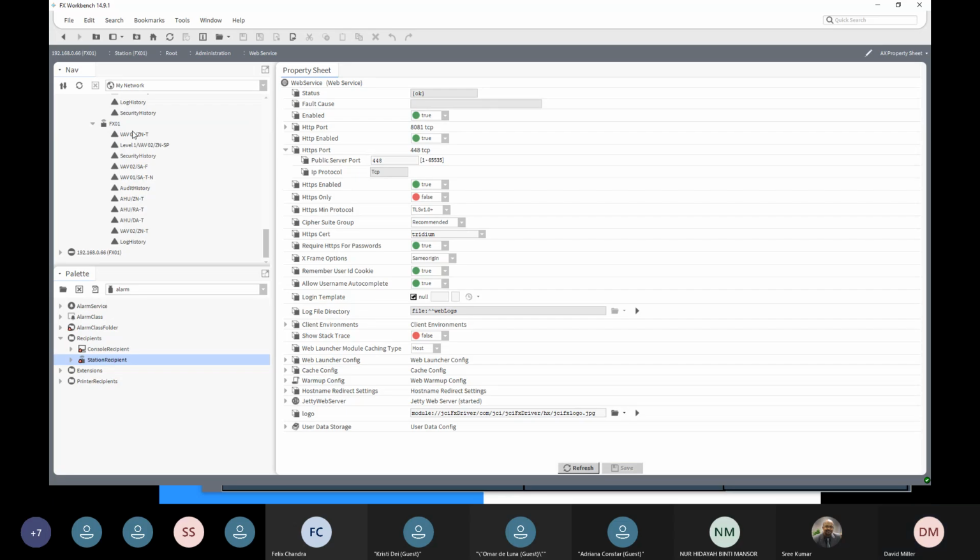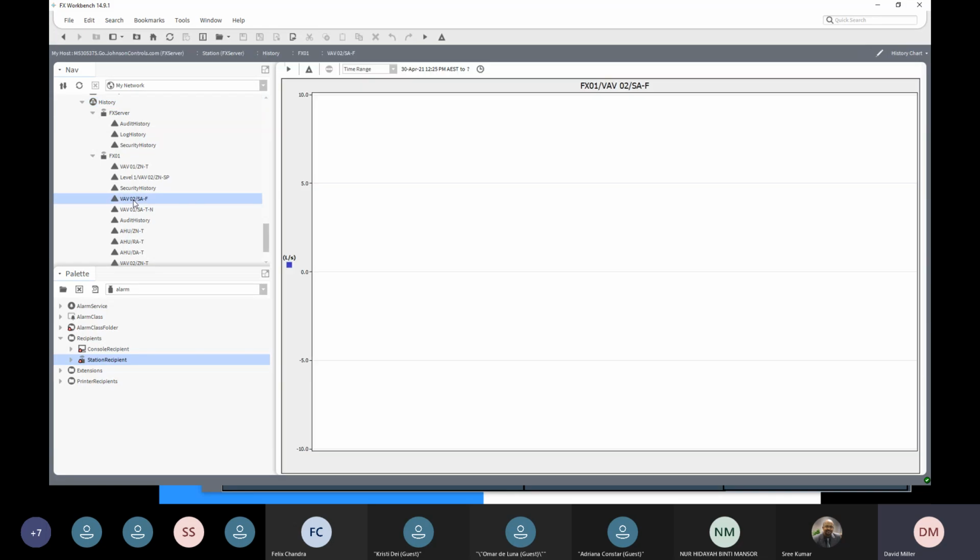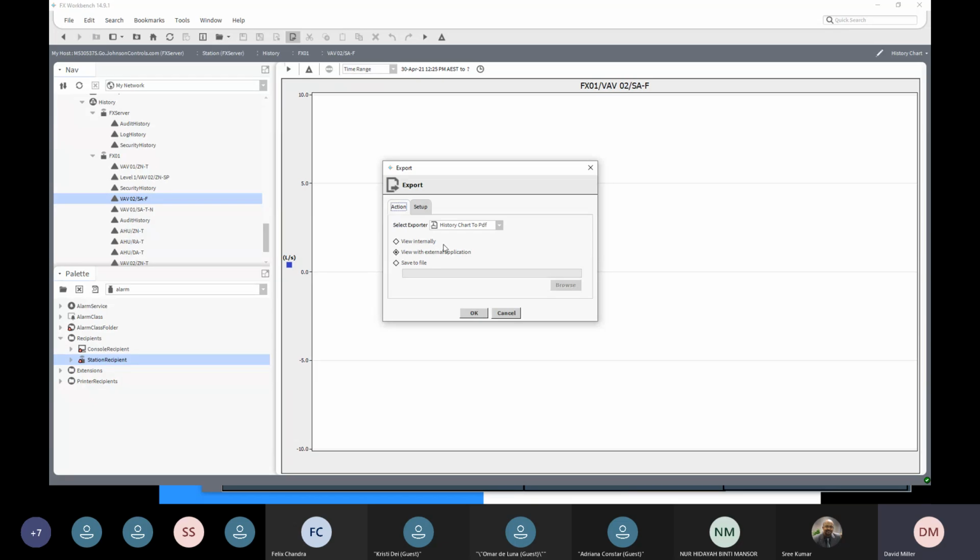It's being saved using the Tridium format or the Facility Explorer format. So the only way that you can get access to this trend or history data is through this interface, or by exporting it to CSV, or you can use the oBIX API. So the data is stored on your hard disk, but it's in a Tridium format.